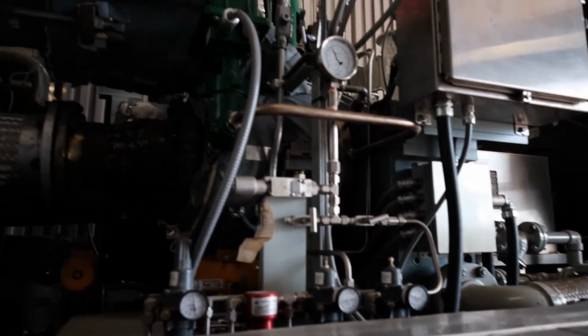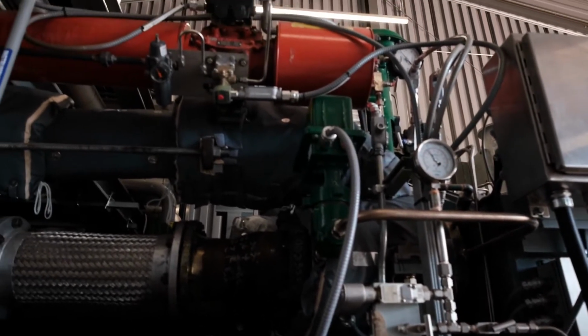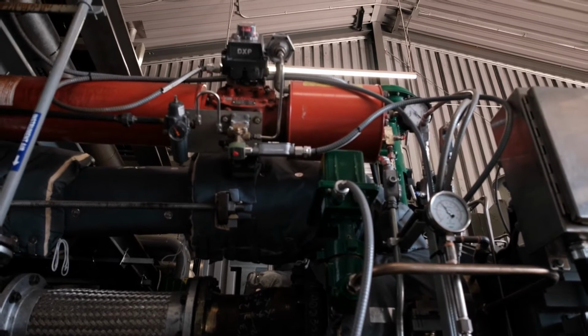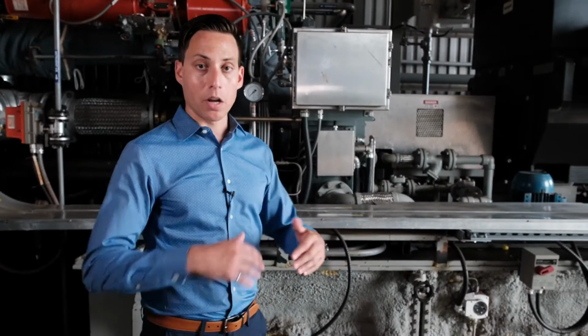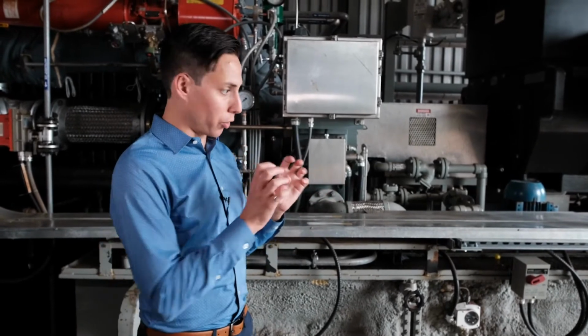The turbine is a 2-stage, integrally geared unit which drives an electrical generator. Each stage has an impeller, which is a highly engineered fan blade, which is spun by the air that flows through it, providing that power through the rotors into the central gear and into the generator.